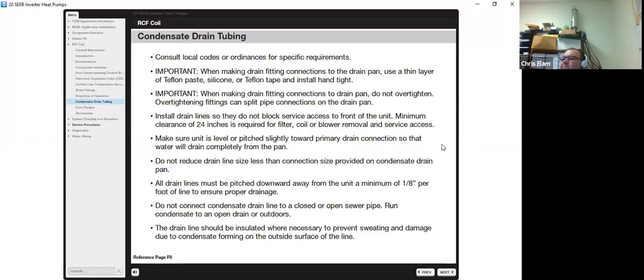Condensate drain tubing. Consult your local codes and ordinances for specific requirements. Install drain lines that do not block service access to the front of the unit. A minimum clearance of 24 inches is required for filter, coil, or blower and service access. Make sure the unit is level, preferably slightly pitched toward the primary drain connection, so the water will drain completely from the pan. Once again, do not reduce the size of the drain line.